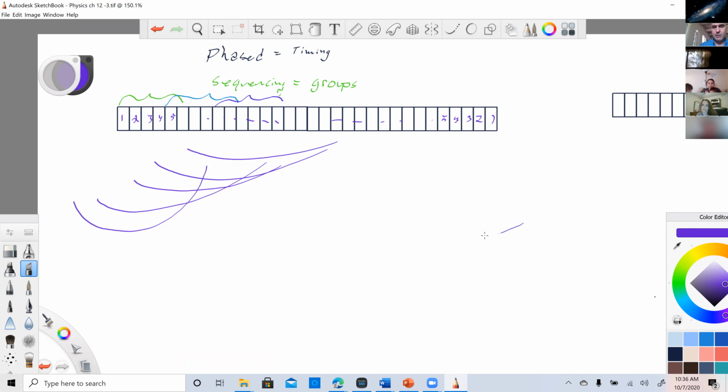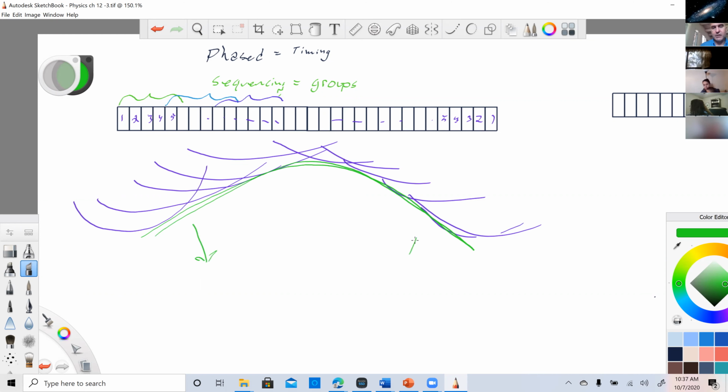And then the same thing over on this side. Obviously, I've missed a lot of them, but now we've created our electronic focus down to there. That's phasing. So what I just accidentally did, and that's okay, I used the entire transducer to focus a beam. By making that accident, I've actually made this transducer into a linear phased. The whole face was used. But that's not how this one works, right? Because we're actually talking about linear sequenced.